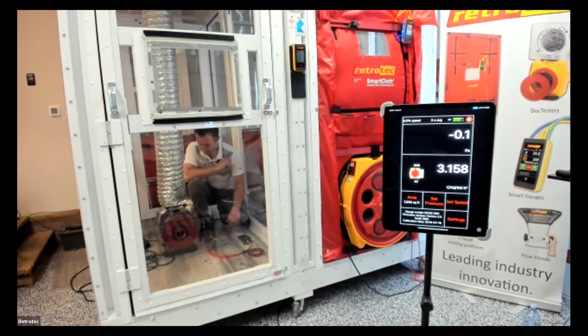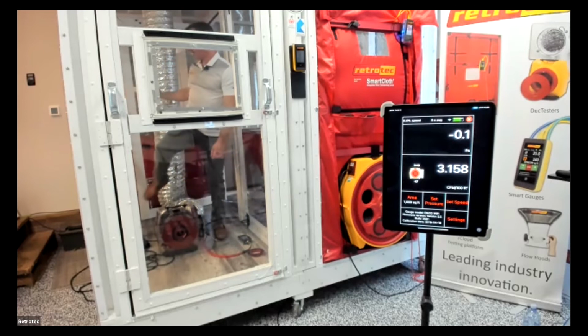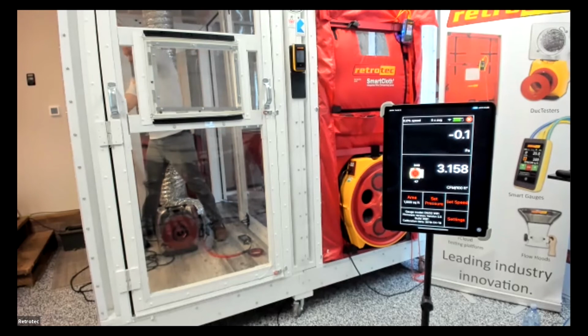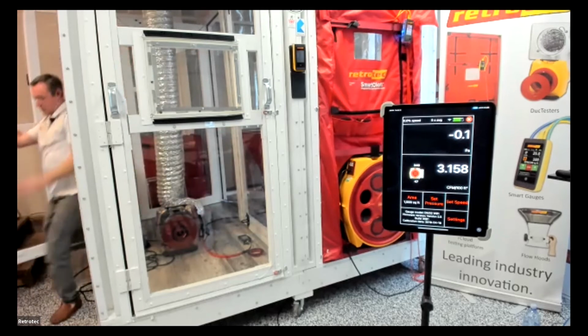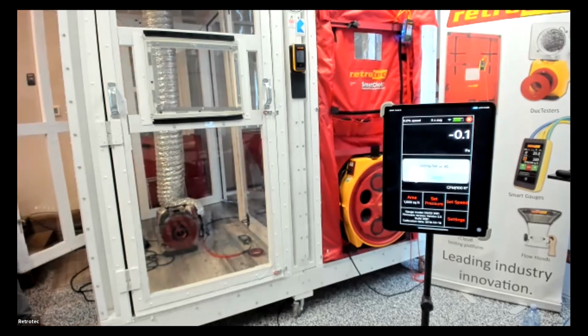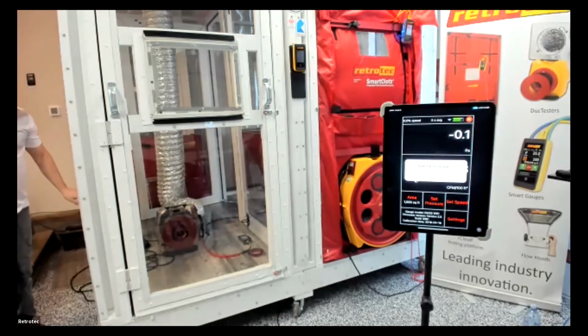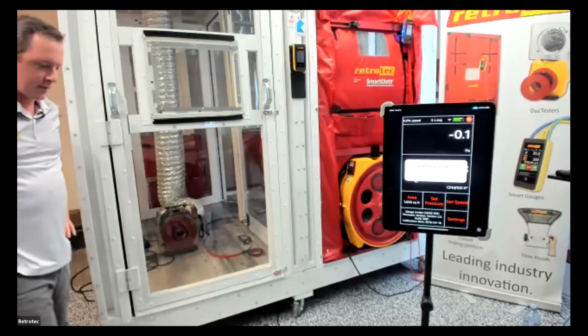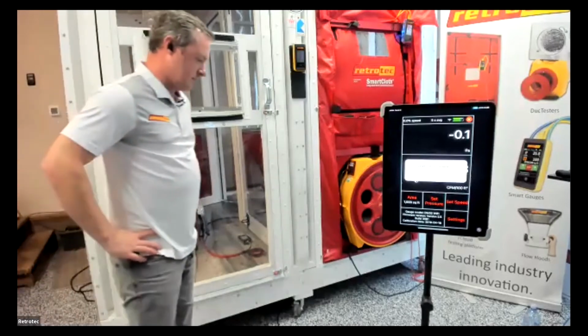So Sam, yeah, you're following that rule of thumb where if you can't get to your target pressure and the fan's maxed out, you go up a range. But if you can get to your target pressure and you're getting no flow result, you go down a range. Even though we're setting to 0, it's that same rule of thumb.